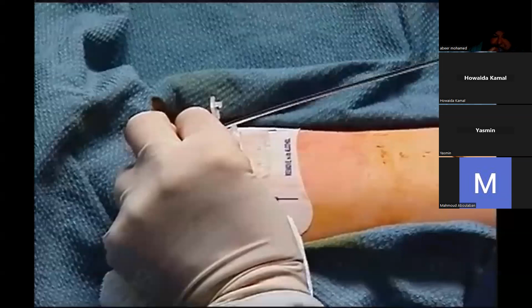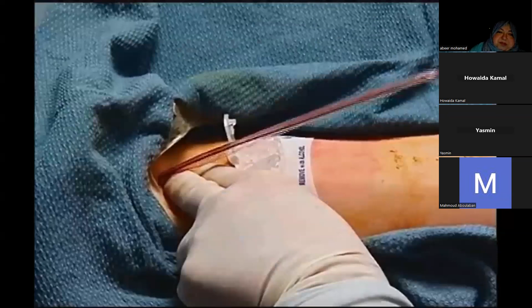Intra-aortic balloon membranes may be penetrated during the course of balloon therapy. Calcified plaque in the aorta may abrade the balloon surface, leading to membrane penetration. Large penetrations are rare, but on suspicion of a leak, the balloon should be removed immediately. If blood is seen within the balloon catheter tubing, stop pumping and remove the balloon. The IAB catheter should not remain inactive, that is, not inflating and deflating, for more than 30 minutes because of the potential for thrombus formation.